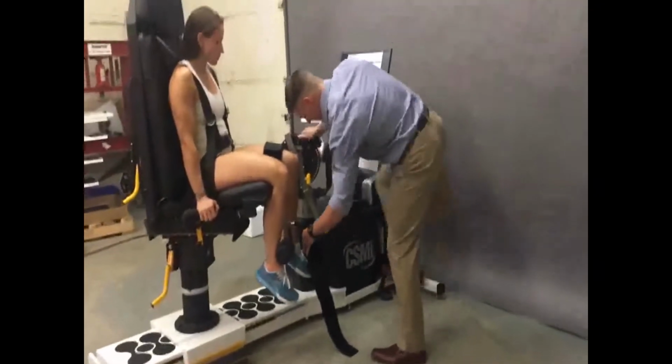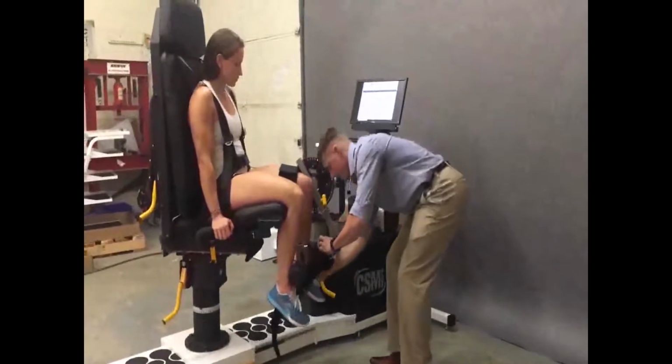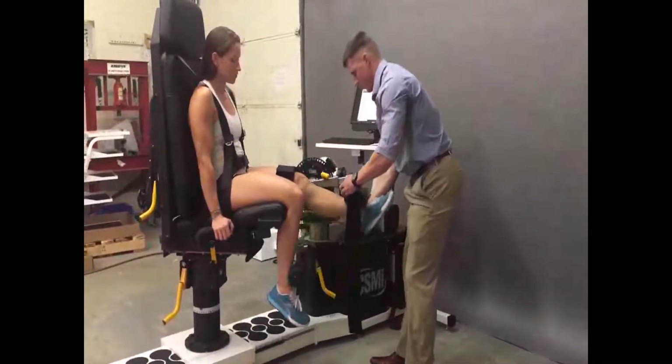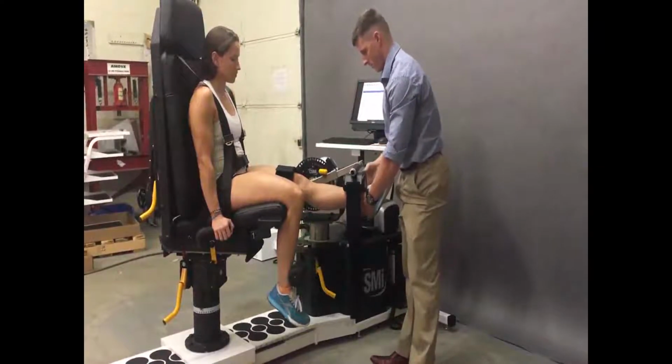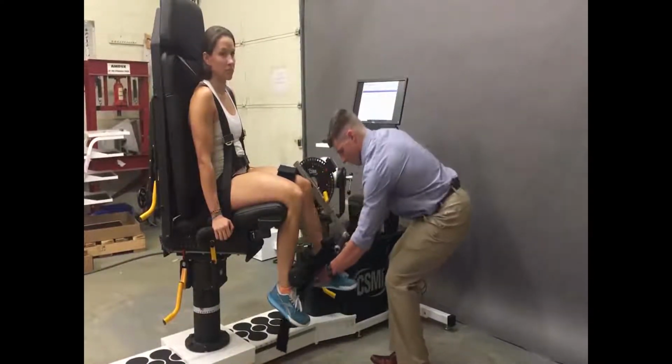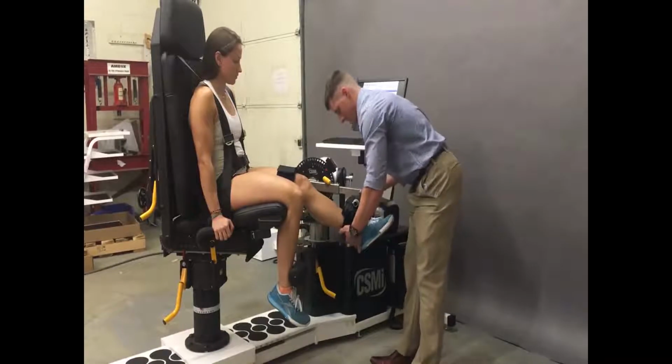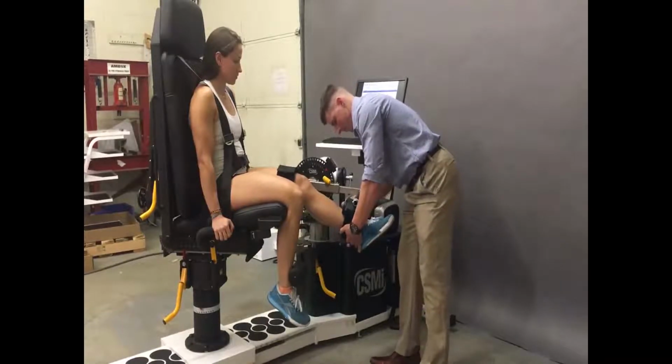Now that you're over here, go ahead and move the dynamometer to rotation at the 40-degree line. If you didn't move it beyond the 40, when you swing the patient over, you would have hit their leg up against that adapter. So you always have to adjust that after. Once you're there, check your alignment.